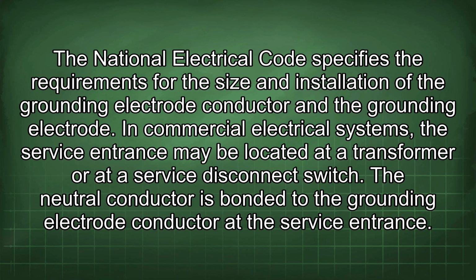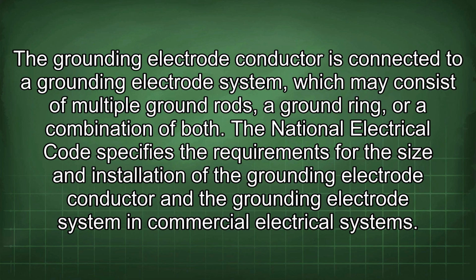In commercial electrical systems, the service entrance may be located at a transformer or at a service disconnect switch. The neutral conductor is bonded to the grounding electrode conductor at the service entrance. The grounding electrode conductor is connected to a grounding electrode system, which may consist of multiple ground rods, a ground ring, or a combination of both. The National Electrical Code specifies the requirements for the size and installation of the grounding electrode conductor and the grounding electrode system in commercial electrical systems.